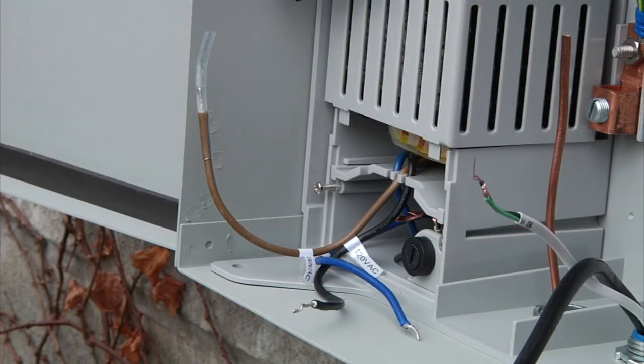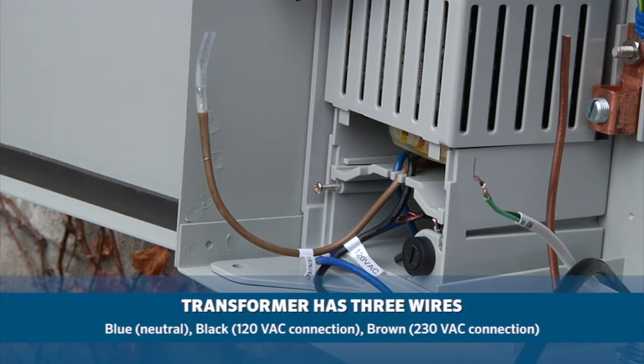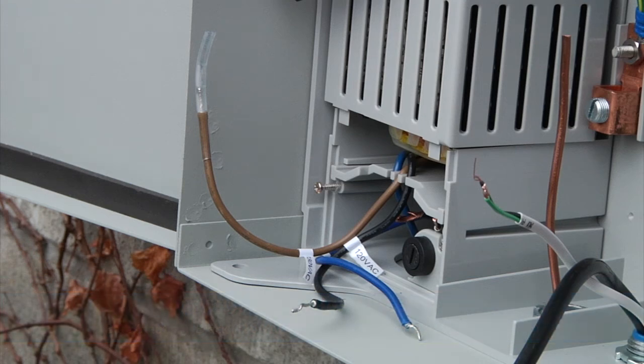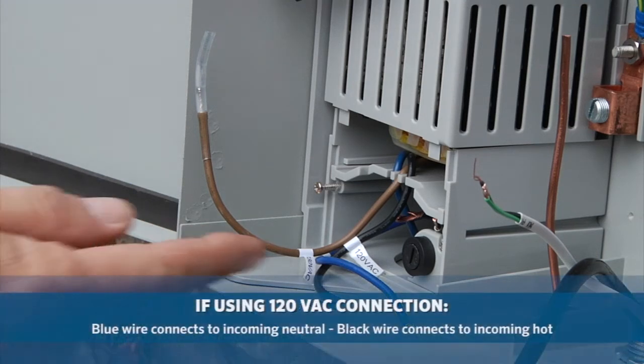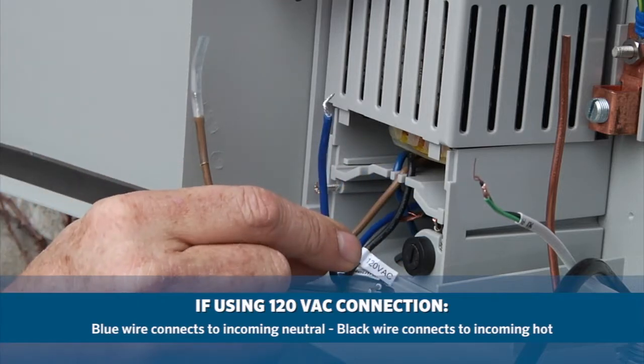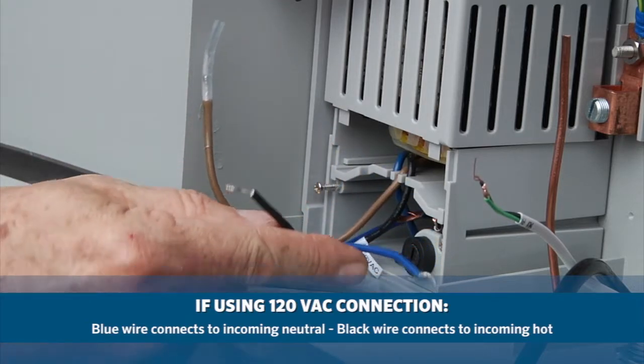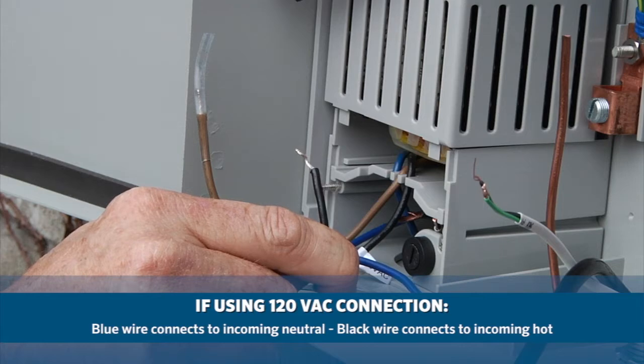So when the electrician opens the junction box, he's going to find 3 wires coming out of the transformer. The blue is the neutral wire, the black is the hot wire for the 120 connection, and the brown wire is for the 230 connection. So you'll need to decide what power source you're using, either 120 or 230. If it is the 120, you'll use the blue wire, which will connect to your incoming neutral, and your black wire, which will connect to your incoming hot.